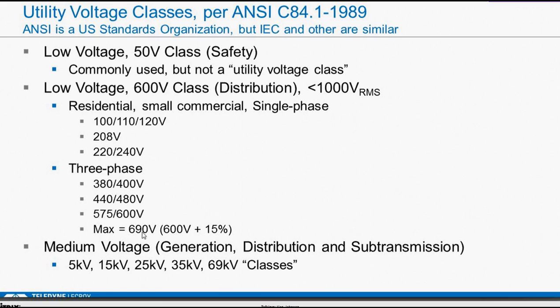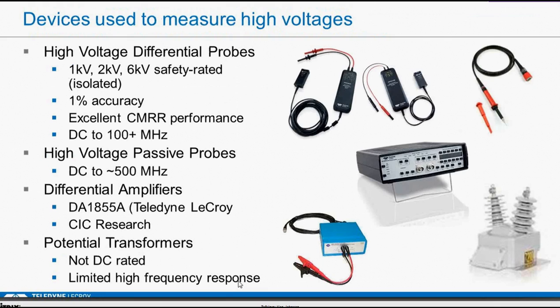The max you could get to this would be 600 volts plus 15%, which would be like a worst-case definition of overload of voltage on the line. And if you did all the math to figure out what 690 volts three-phase rectified would be, it would come out to just under 1,000 volts, which is why this is considered a less than 1,000 volt RMS class. Then you get into medium voltage for generation, distribution, and subtransmission. These are 5 kV all the way up to 69 kV classes. And then for very high voltage, it goes even higher. We're starting to see 1,000 kV or megavolt class equipment being installed.